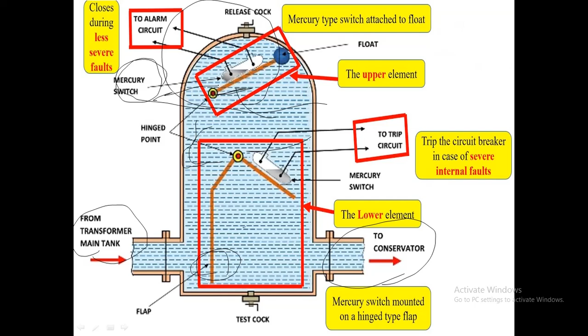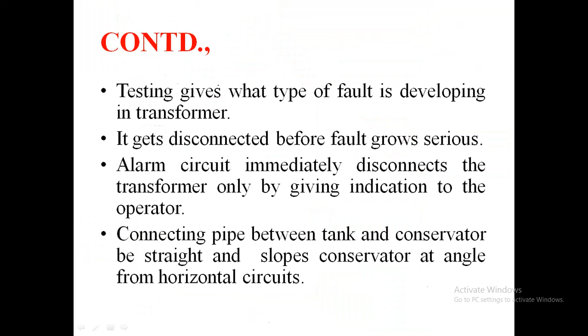The connecting pipe between the tank and the conservator should be as straight as possible and rise towards the conservator at an angle of 10 to 11 degrees, which is enough. For consideration, this relay is not provided for transformers having a rating below 500 kVA.